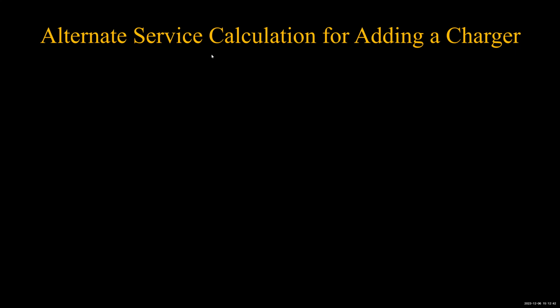There are distribution panels out there now that you can program such that the panel itself will have contactors on every circuit breaker, such that it can shut down that circuit according to, call it the advanced metering infrastructure, because what you're basically doing is watching the total current either flowing in or flowing out from that structure and limiting it to whatever the program says you need to limit to. So yeah, this is the fancy stuff that we're getting into, and that is going to be so much fun.